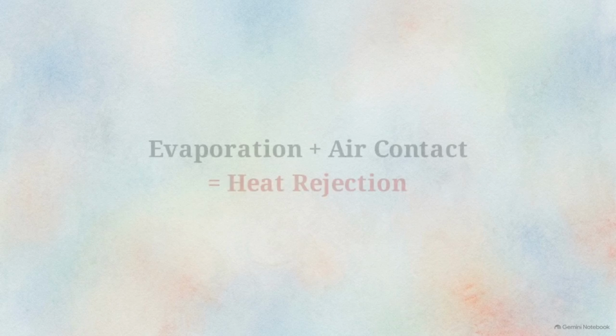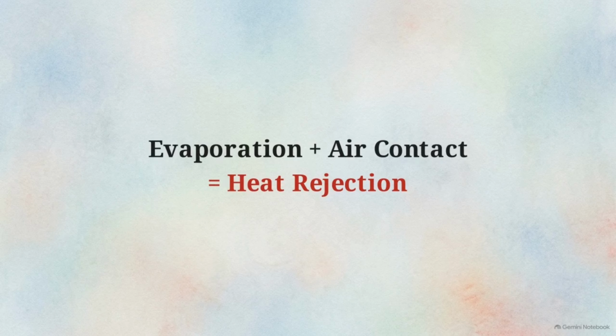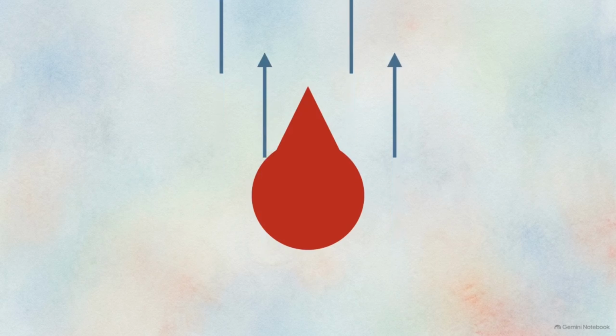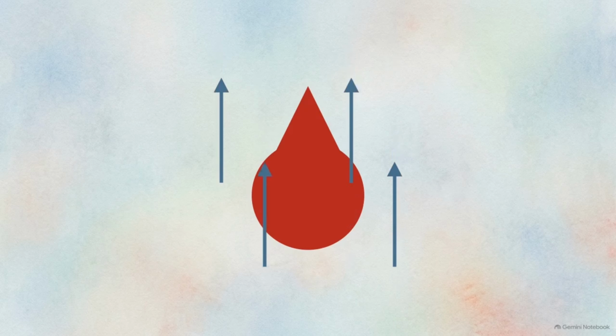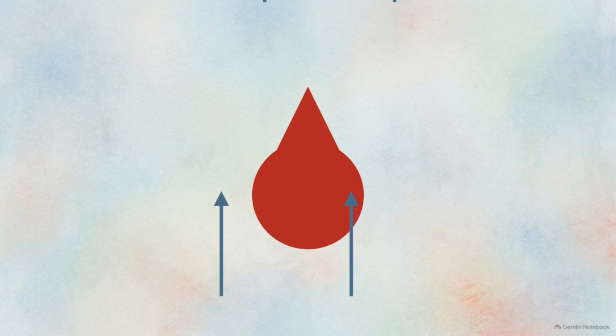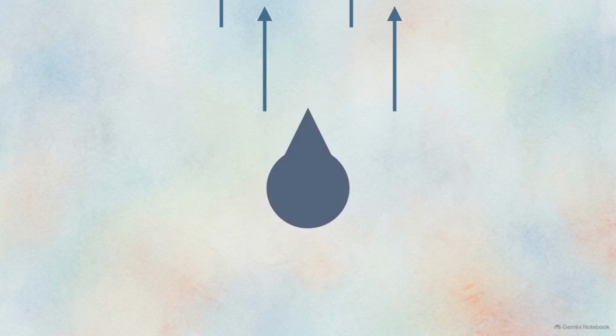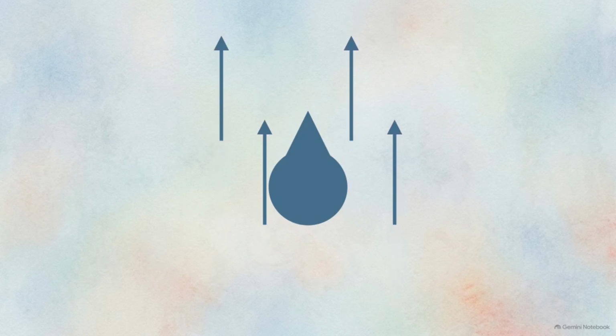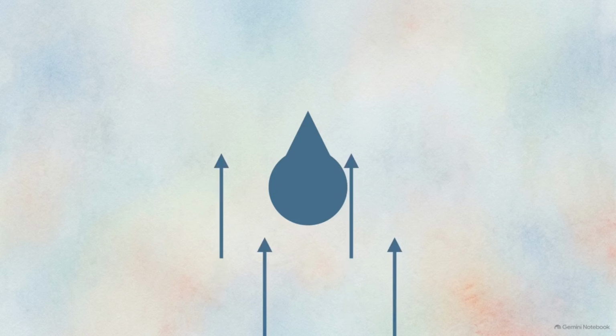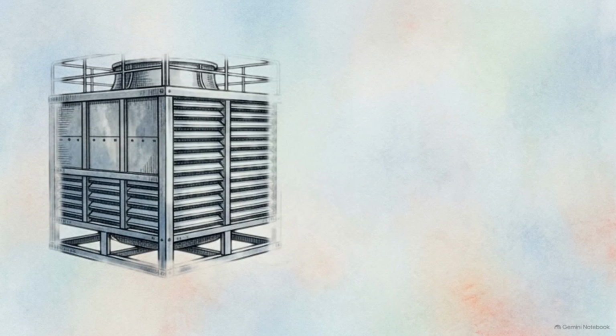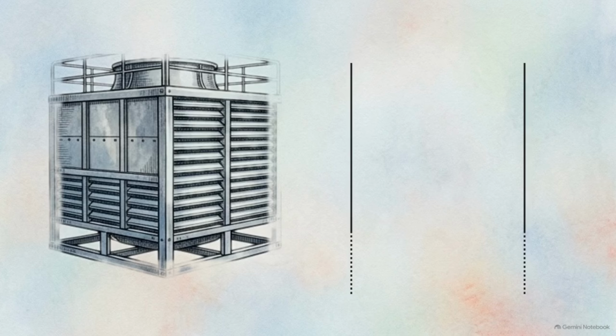The core thermodynamic equation governing a cooling tower is straightforward. Evaporation plus air contact equals heat rejection. While contact with cooler air provides sensible heat loss, the primary mechanism is latent heat transfer. As water evaporates, it extracts physical energy directly from the remaining liquid, driving its temperature down. Evaporating a single drop is easy. The engineering problem is executing this process on thousands of gallons per minute.